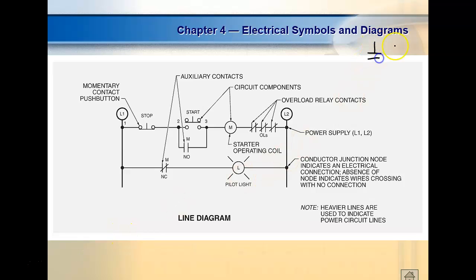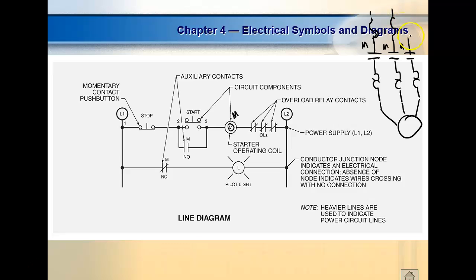So I know over here we got a motor, and I know it's got overload sensors on it that control these contacts right here. And it's a three-phase motor, so we should come in and angle them in and bring them in like that. This relay is given the name M. So I'm going to come up here and give these contacts the name M. Then normally we'll come up and we'll have fuses right here. We might have a disconnect up there, like ours has got a major disconnect up there, right? Okay.